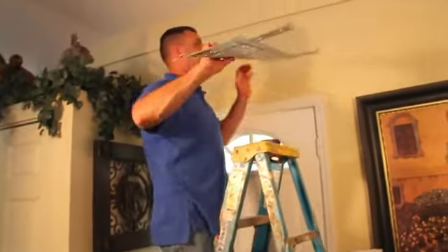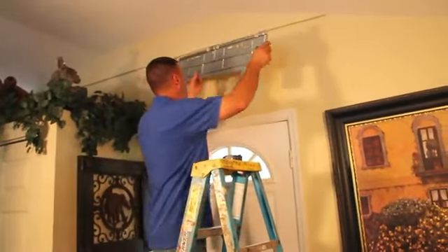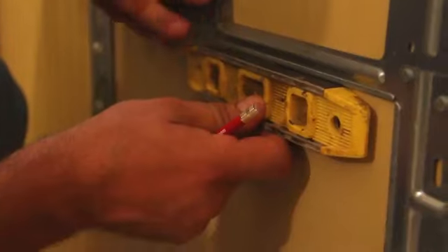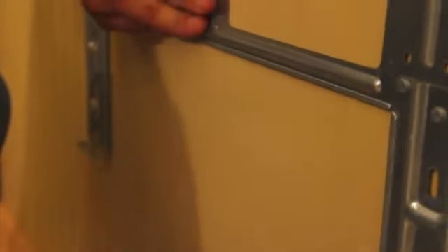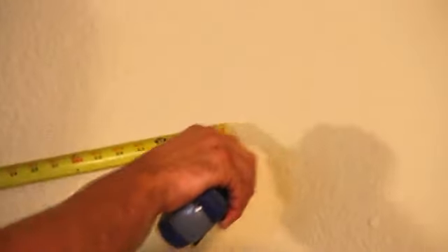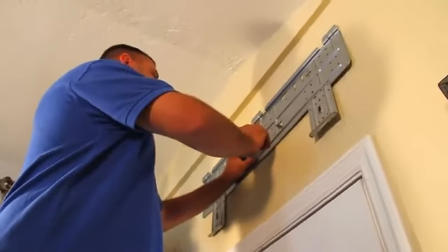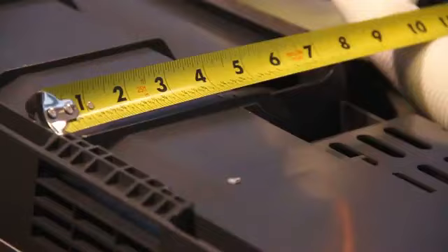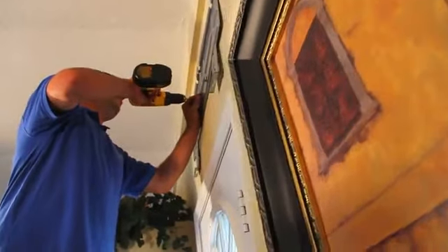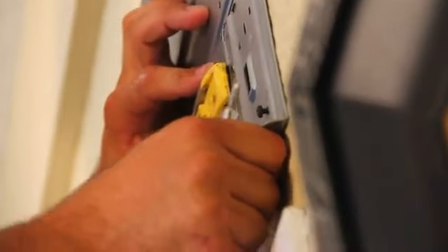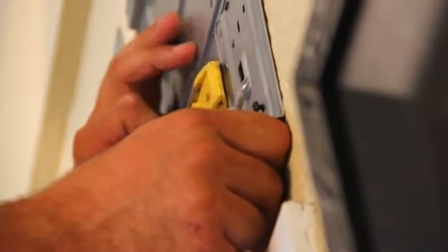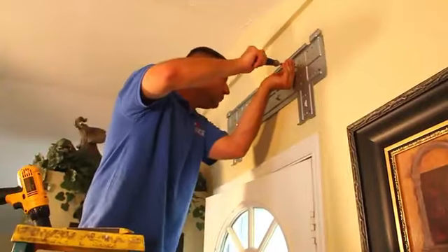Then, pick out a spot on the wall surface where you want the unit to be secured. After you have decided, use a level to mark out drill points and secure the wall mount according to the instructions. You will have to drill holes that are level with one another. Through this process, be sure you have marked the area so that you know where you're going to drill. Measure twice, cut once. It's a carpenter's rule and it works here. For us, we want to measure twice and drill each hole once. One thing our interior walls do not need are unnecessary holes. After you have measured, drilled, and installed the wall bracket, make sure the latch points are secure. The last thing you want is for the mini-split to tumble off the wall.